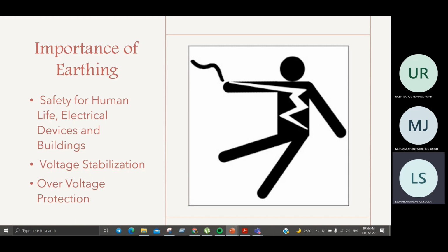importance is voltage stabilization. As for voltage stabilization, electricity comes from many sources; every transformer can be considered a separate source. If there is no point which will act as a common point, then it is impossible to make a calculation between these sources. So earthing will represent the common point. In an electrical distribution system, earth is an omnipresent conductive surface, which makes it a universal standard for all electrical systems. And finally, over voltage protection. Earthing also provides an alternative path in the electrical system to minimize the dangerous effects which happen at the time of lightning and unintentional contact with high voltage lines.